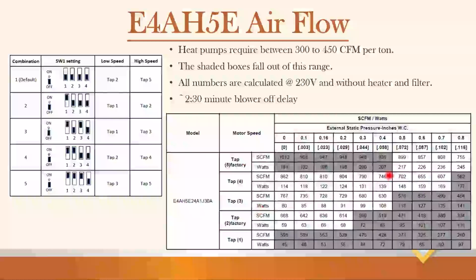This is a 2-ton unit. We'll put out 702 CFM. At 0.7, look how much CFM. So you're not getting as much. So we might want to increase the ductwork to lower that static pressure so we can get some more CFM. So as you can see, that's how that works. So you definitely want to pay attention. Tap 5 is high speed, right? So factory default is tap 2 and tap 5. This is our low speed, tap 5 is our high speed.